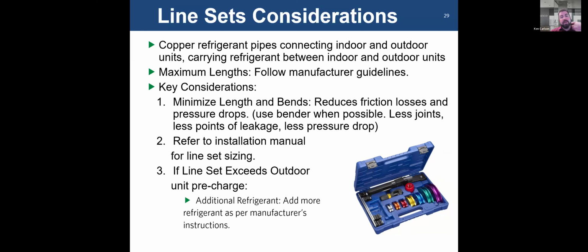You want to reduce frictional losses and pressure drops as much as you can. So one of the best ways to do this is to use a pipe bender. Avoid putting in joints. Use a pipe bender when at all possible. It's one less connection you've got to braze. If you can get away without any connections, and it's just flare connections, no bend, no brazing joints, you don't have to worry about purging. It saves time. It also reduces pressure drops. It's a much smoother bend as opposed to putting in a fitting with abrupt changes in direction or even obstructions from the fitting connections. Refer to your installation manual for line set sizing.